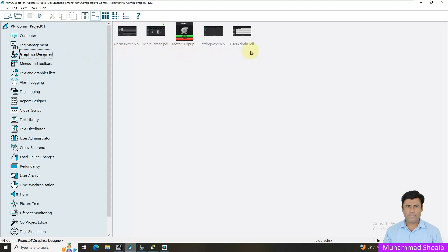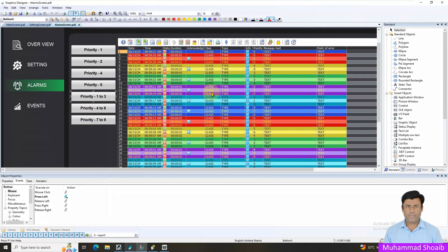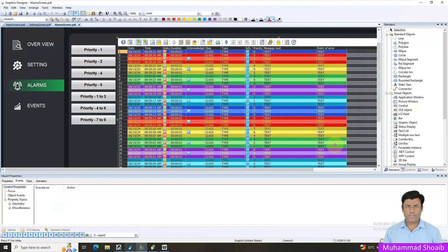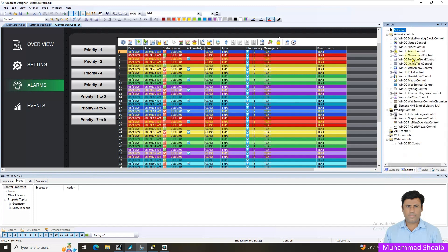Now I will open the Graphic Designer and open my alarm screen. Here I have created some multiple buttons. I put a VB script on each button. To create a VB script, you go to Events, then Mouse, then Press Left, right click and select VBS Action. Here I take the screen item — 'Control1' — which is our alarm control object. In our previous tutorial video we already learned to drag and drop the alarm control here. To find the object name, click on the alarm control in the Properties panel.